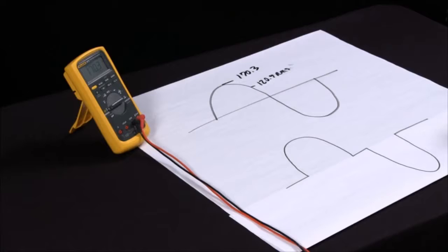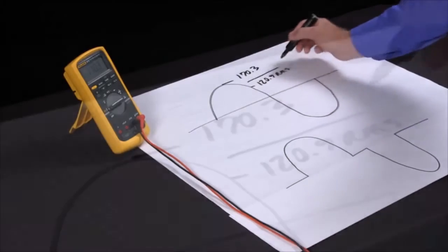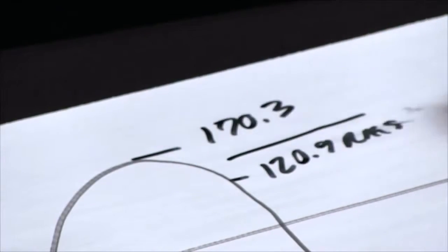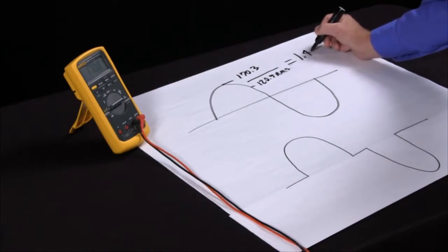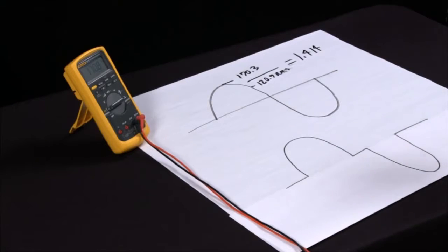Now there's something called the Crest factor, which if I divide the RMS into the peak on a nice clean sine wave, this should come to 1.414. Now we can all divide 120.9 into 170.3 and come up with 1.414.